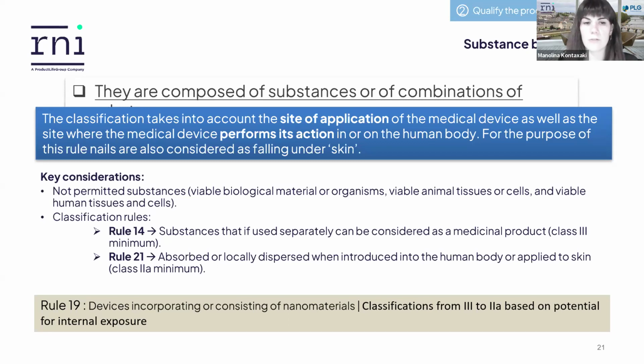Another rule that is really critical is Rule 21, which is a new classification rule in the medical device regulation. This rule speaks about the absorption and the local dispersion of the medical device when it is introduced into a body orifice or applied to the skin. This classification rule classifies the medical devices at minimum as Class 2A. We are going to see a bit more detail on this later.